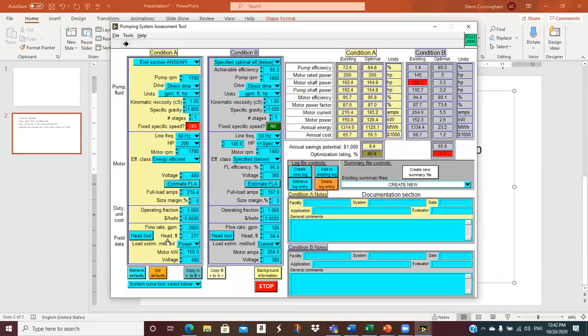We'll leave that unchanged. All right. That's pretty much for this right now. For example, let's say this was our base case. You can copy A to B, which is nice, and it just makes these two the same. And then let's say I've got a valve that's throttled in this thing. Maybe I've measured the pressure loss across the valve. So what I'm going to do is trim the impeller, because the pump's too big, so they've got the valve like 50% shut. So I'm dropping a bunch of pressure across the valve to move me up the pump curve. So by hook or crook, I figure out what the pressure loss is across the valve.